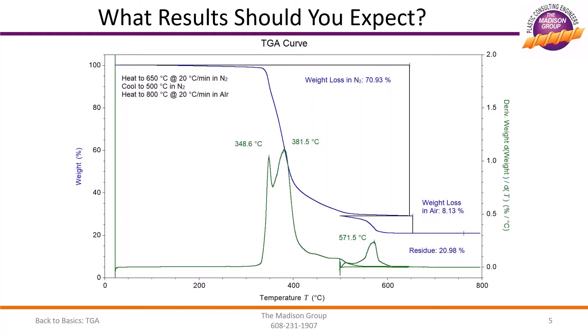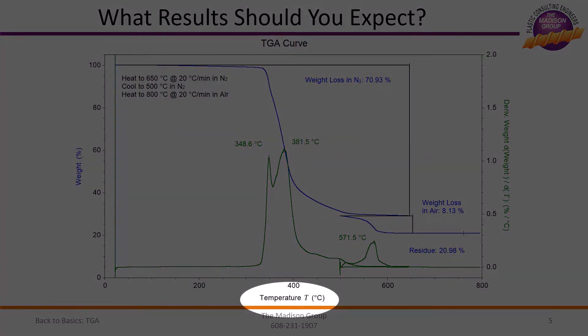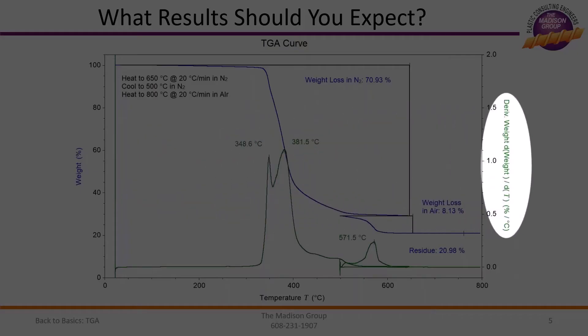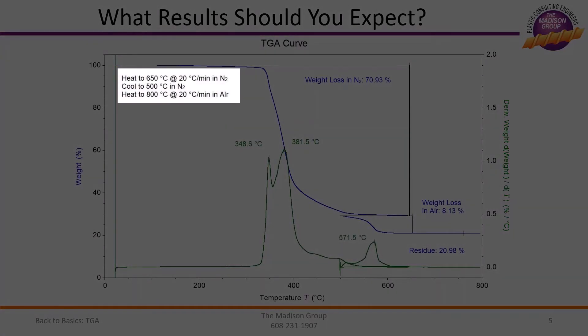This is a typical graph outputted from a TGA test of a polymeric material. This graph is plotted with temperature on the horizontal axis, although some analysts prefer to plot TGA results with respect to time. The percentage of the original weight remaining, called the weight percent curve, is plotted on the vertical axis. Additionally, the derivative curve of the weight percent with respect to temperature is also plotted, with its scale shown on the right vertical axis. This experiment involved heating the sample to 650 degrees C in an inert nitrogen atmosphere, then cooling to 500 degrees C in nitrogen, and finally switching to an oxygen-rich air atmosphere and heating to 800 degrees C.